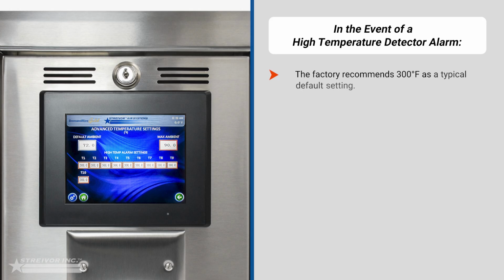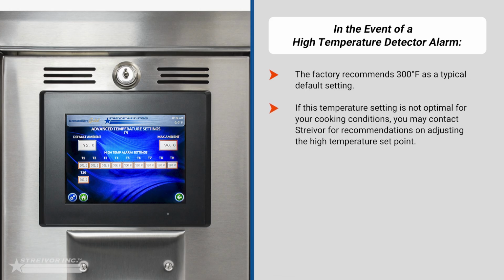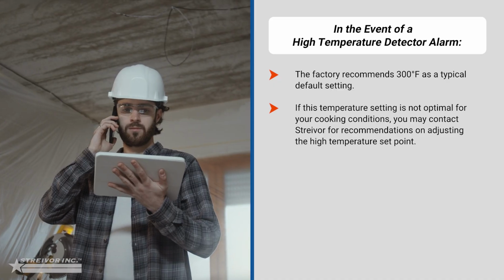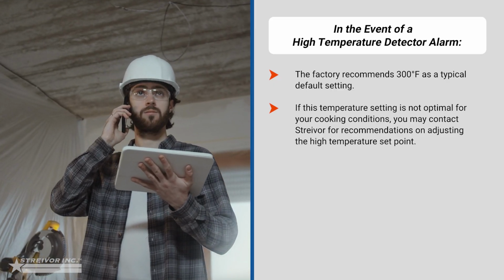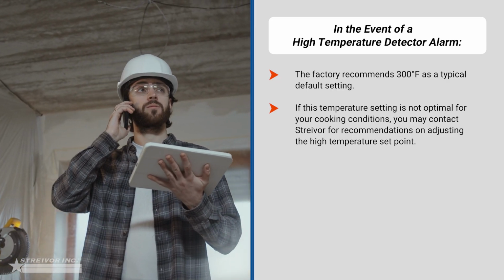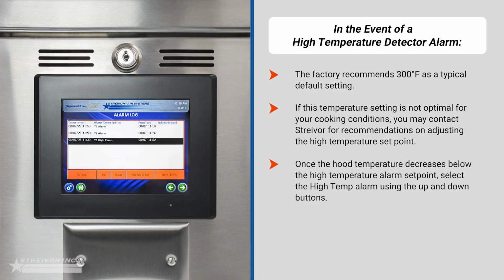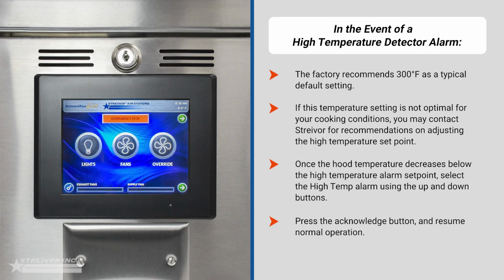The factory recommends 300 degrees Fahrenheit as a typical default setting. If this temperature setting is not optimal for your cooking conditions, you may contact Streivor for recommendations on adjusting the high temperature set point. Once the hood temperature decreases below the high temperature alarm set point, select the high temp alarm using the up and down buttons. Press the Acknowledge button and resume normal operation.